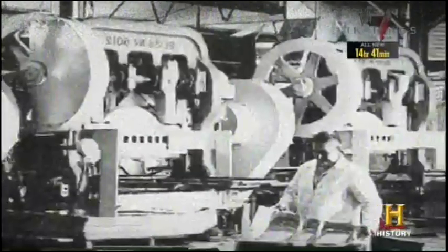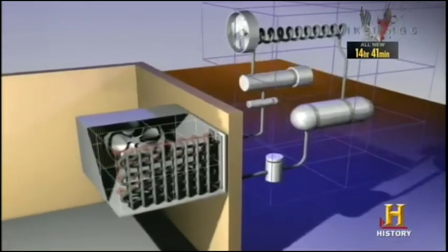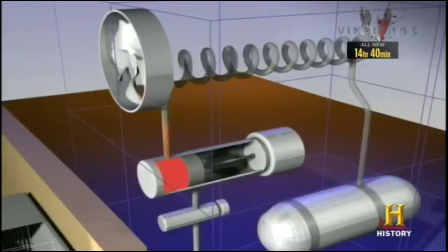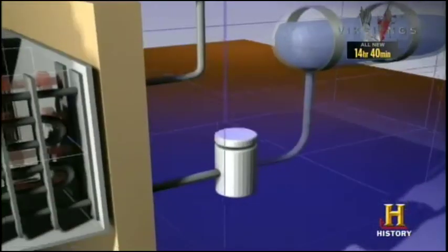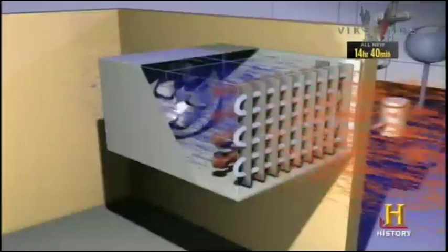Goettl Air Conditioning was the first to adapt Willis Carrier's 1902 invention to the Phoenix area. Its units weren't cheap, but they did the job. An air conditioner is basically a refrigerator without the insulated box. A compressor pressurizes a refrigerant, usually Freon gas. The pressure forces it to heat up. This hot gas runs through a set of coils to dissipate its heat, condensing it into a liquid. The liquefied Freon then runs through an expansion valve, where it evaporates to become cold, low-pressure Freon gas. This cold gas runs through a set of coils that allows the gas to absorb heat and cool down the air inside the building.